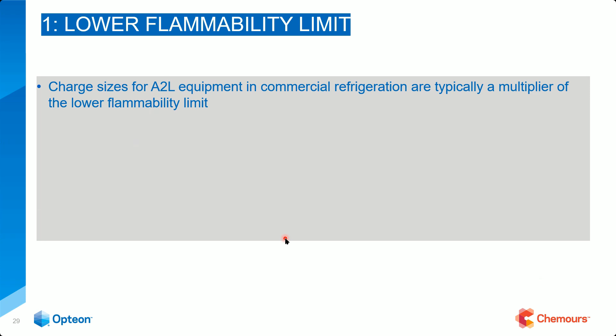Charge sizes for A2L equipment in commercial refrigeration are typically a multiplier of the lower flammability limit. Just to bring you up to par on what LFL means: there's a lower flame limit and there's an upper flame limit. Until it hits the lower flame limit, it can't even become flammable. In other words, in that flask we were talking about earlier, where we were adding the concentration of the refrigerant to the air and then hitting it with electrodes or some way to ignite it, it's not even flammable until it hits LFL. So this is the lower flame limit.